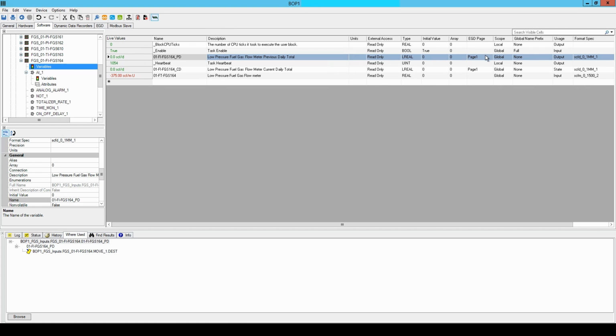Now, if I didn't require the prior day to be added to EGD, for example, if it had already been on EGD, I could do a build without having to download a controller to use. The historian deadband is for the workstation that is functioning as the historian to use. So when I build, that is published to the EGD server, and the flag on that says it's historical. Then the workstation that is configured with PI or the GE historian will catch that flag, change its configuration to update it to start historically collecting that data. And in that way, that data will now be available historically.